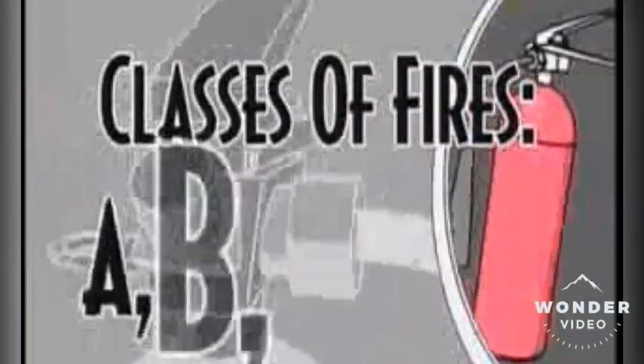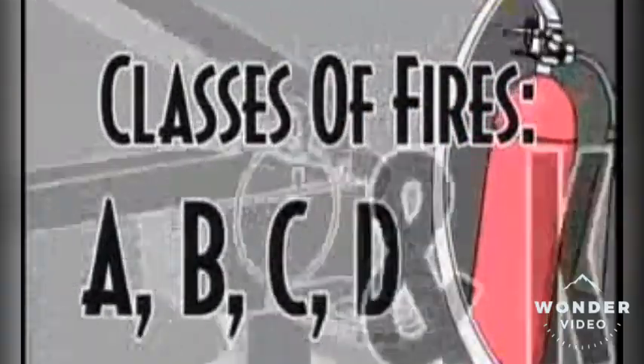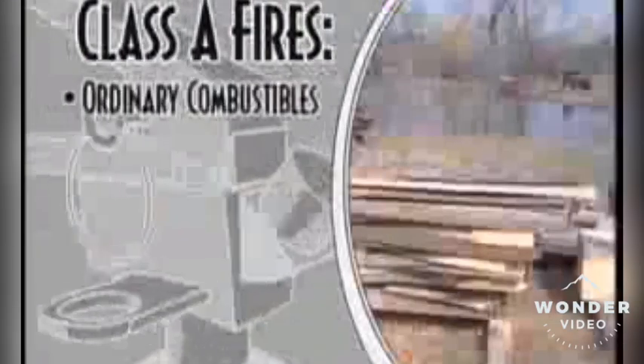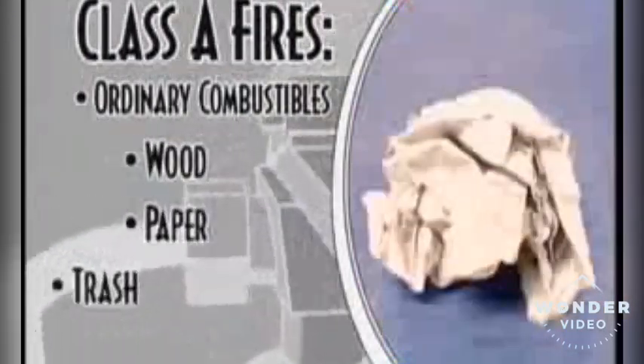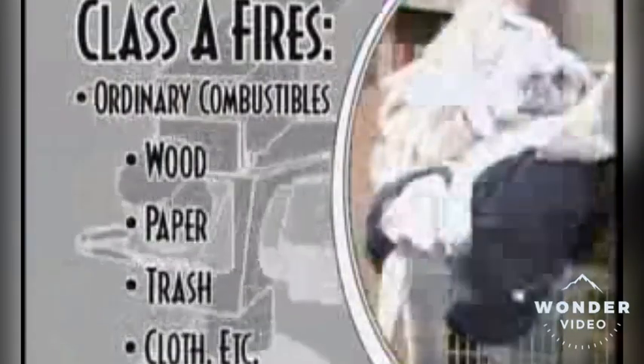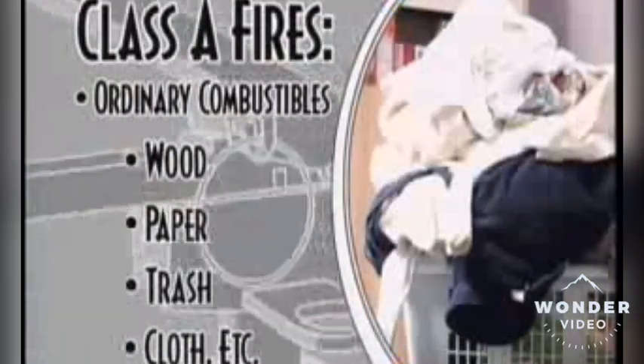The classes of fire are A, B, C, D, and K. Class A fires are those in materials like wood, paper, trash, cloth, and other ordinary combustibles. These fires can be extinguished by extinguishers labeled with the letter A inside a triangle and/or a picture of burning trash.